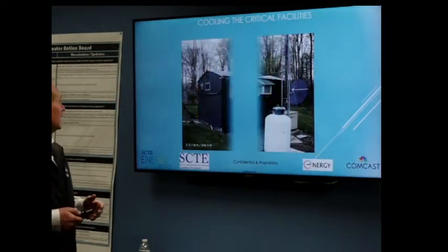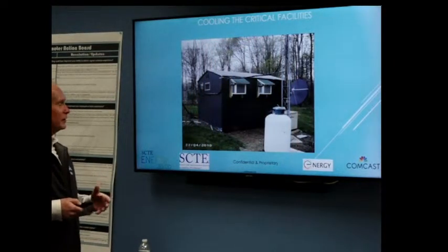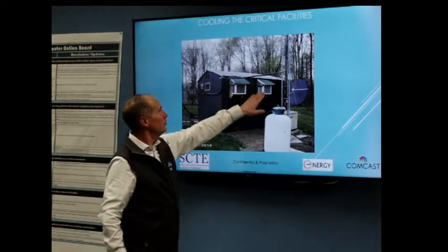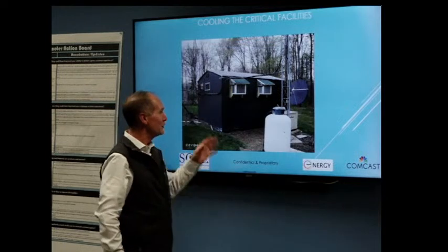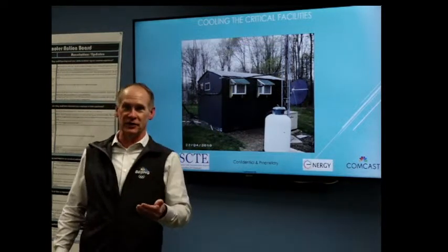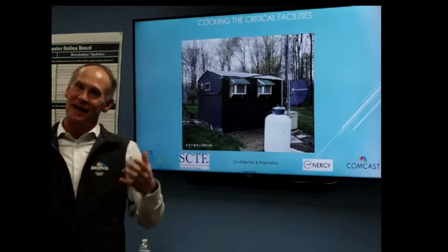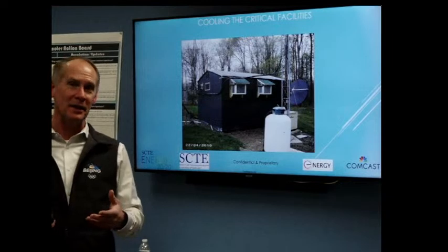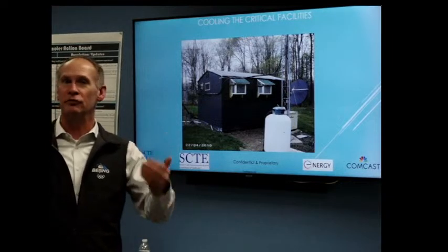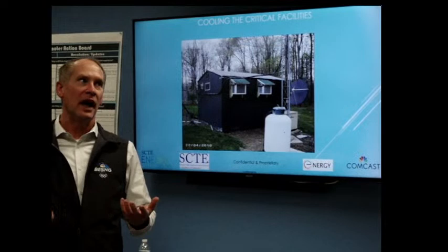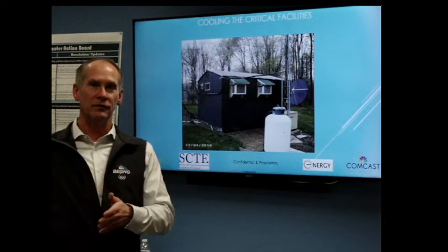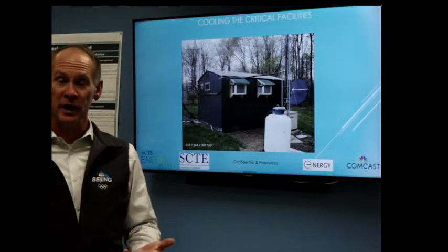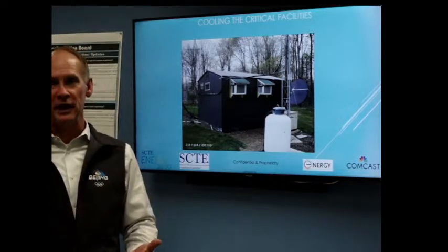So as we see some of the infrastructure for cooling today, it sounds a little bit weird, but these 2 window units cooling this building, granted this building is a legacy building that's only got a one-way system on it, that was probably the right financial decision for that building at that time. It was cheap, it was simple, it was reliable. The technology and the hardware within that critical infrastructure facility was not really needing a conditioned space. It was just needing a cool space.